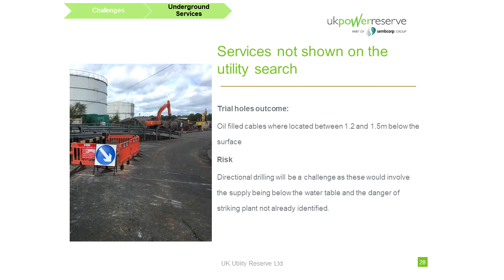Looking at it, my first risk was down to installing those utilities, with the fact that most of the underground utilities were not captured. So I immediately instructed trial holes to be carried out. But when the trial holes were carried out, the outcome was that oil filled cables were found 1.2 meters and 1.5 meters below the ground surface. But yeah, that's fine.